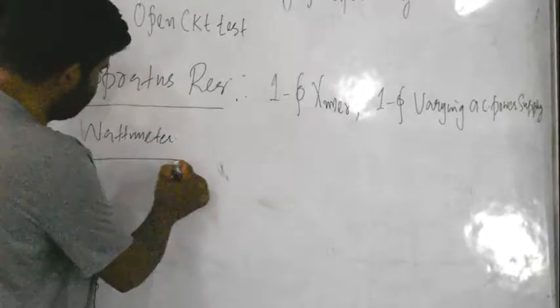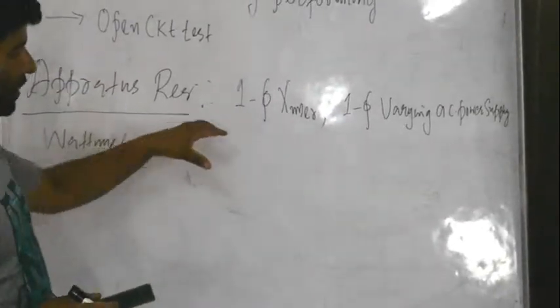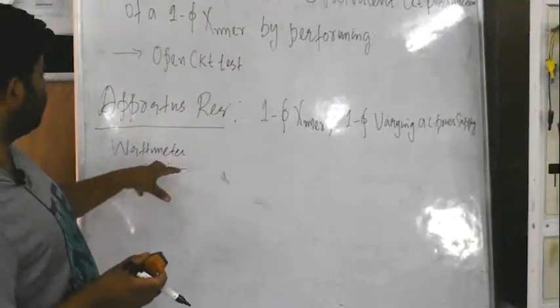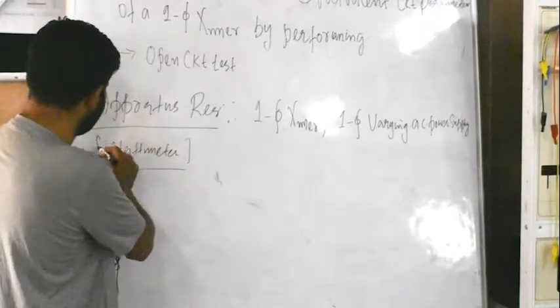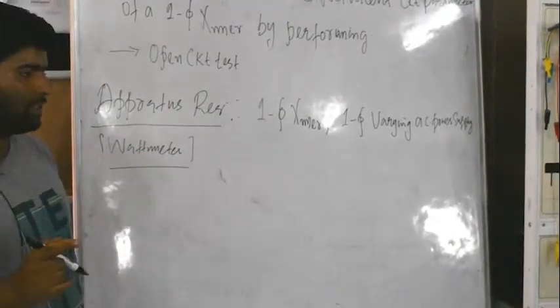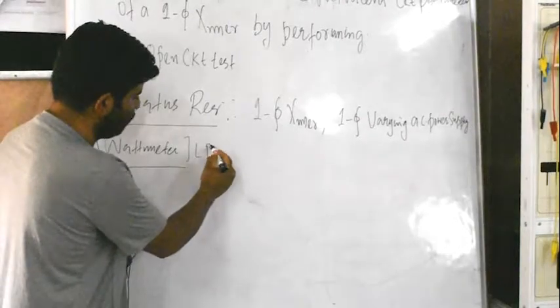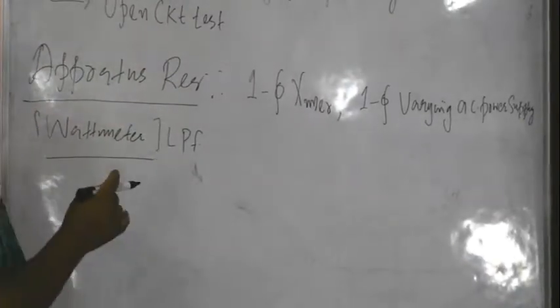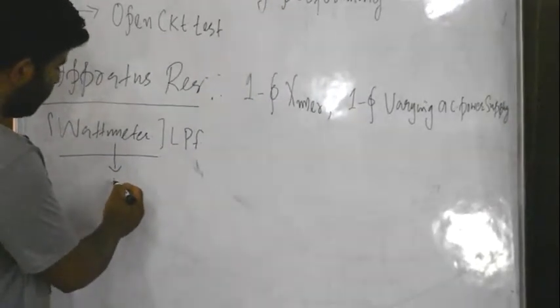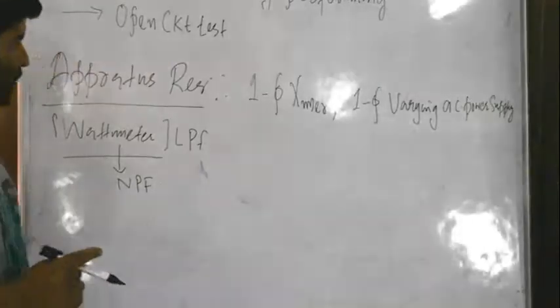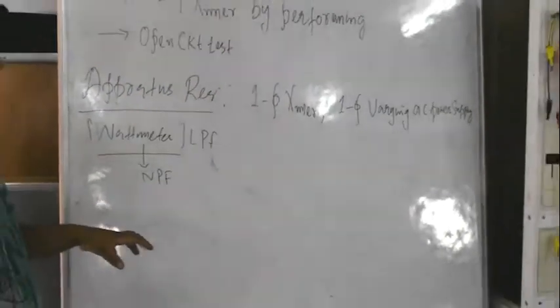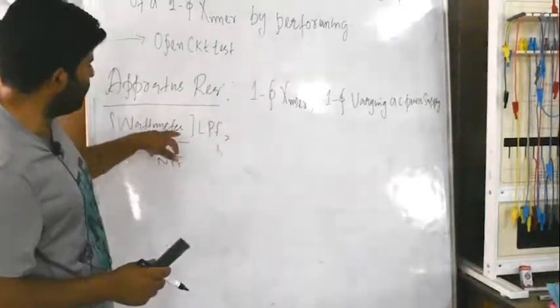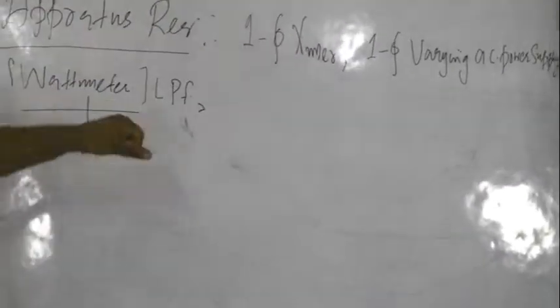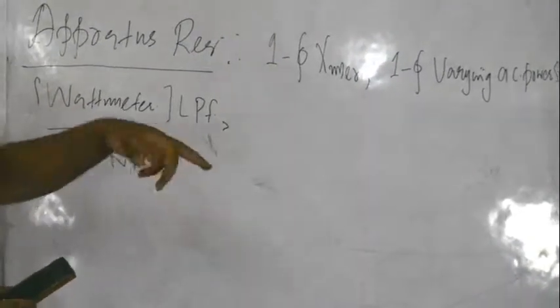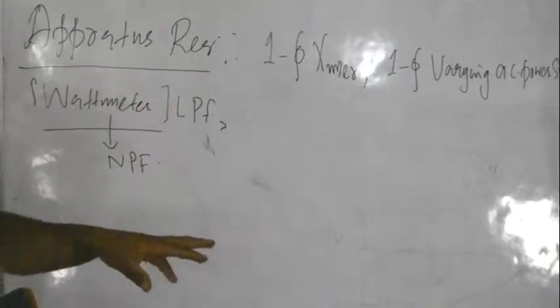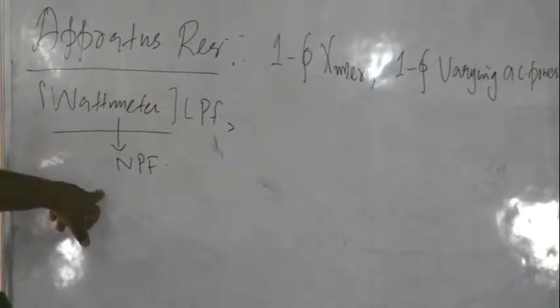As I have already mentioned, the apparatus required in both the tests will be the same, but the difference will be in the measuring equipment, the wattmeter. In the open circuit test, we will require a wattmeter of LPF, that is low power factor wattmeter, while in the short circuit test we will be using a normal power factor wattmeter. This will be the difference in the apparatus required. I will repeat, the wattmeter in the open circuit test will be a low power factor wattmeter, and I will demonstrate how they differ, and in the short circuit test we will be using the normal power factor wattmeter.